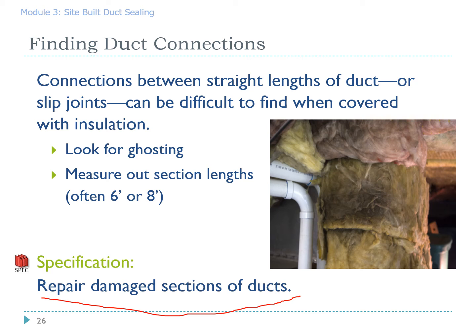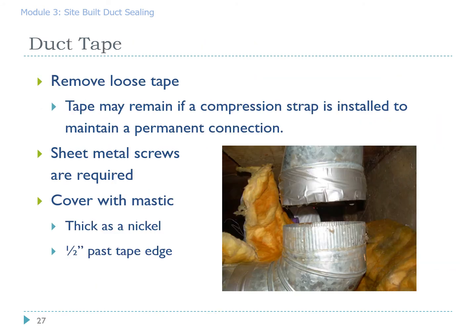A roll of duct tape is a very useful thing to have in your toolbox or behind the seat in your truck. It can temporarily hold just about anything together. The key word there is temporary. It is not a good way to permanently seal ductwork. According to the specs, you must make a good faith effort to remove all loose tape, and we realize that sometimes you can't. We make provisions for that, but the good faith effort must be made.